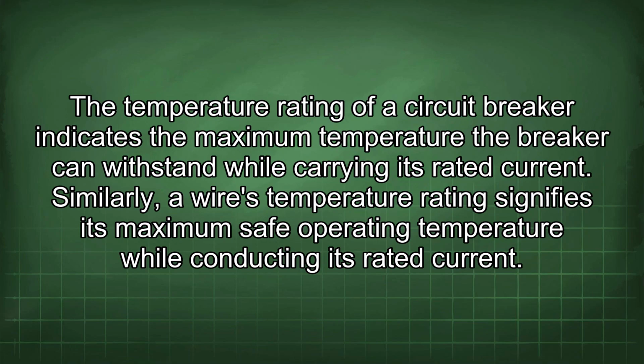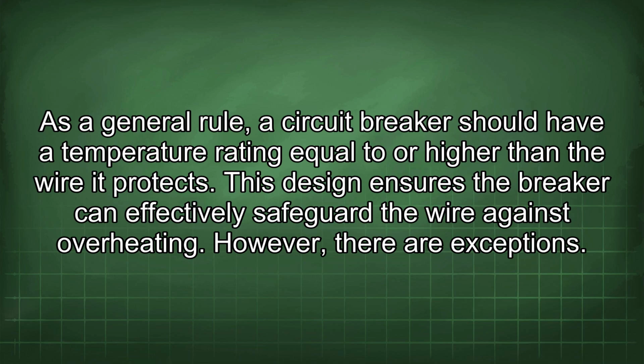The temperature rating of a circuit breaker indicates the maximum temperature the breaker can withstand while carrying its rated current. Similarly, a wire's temperature rating signifies its maximum safe operating temperature while conducting its rated current. As a general rule, a circuit breaker should have a temperature rating equal to or higher than the wire it protects. This design ensures the breaker can effectively safeguard the wire against overheating.